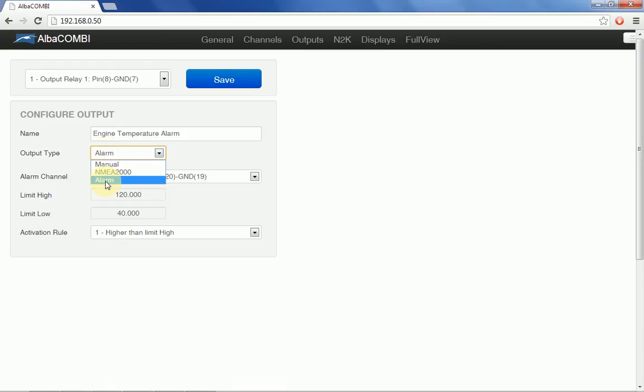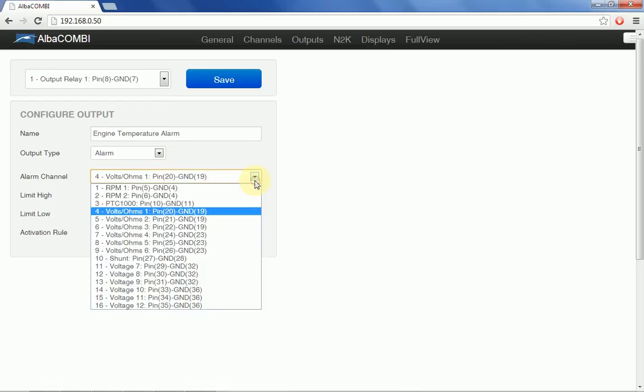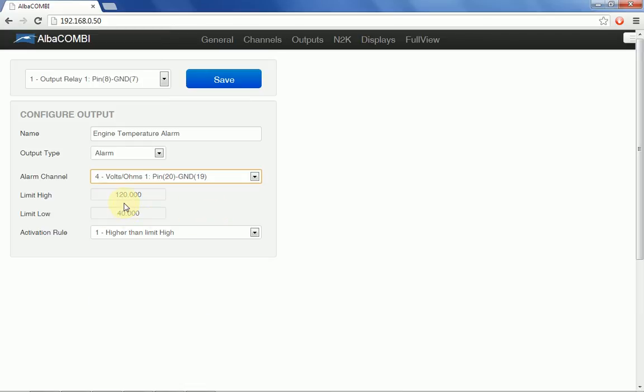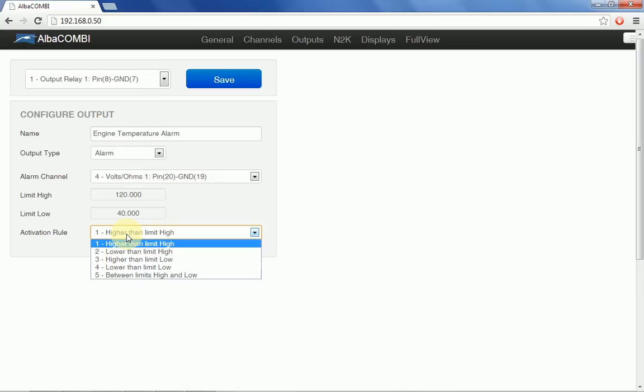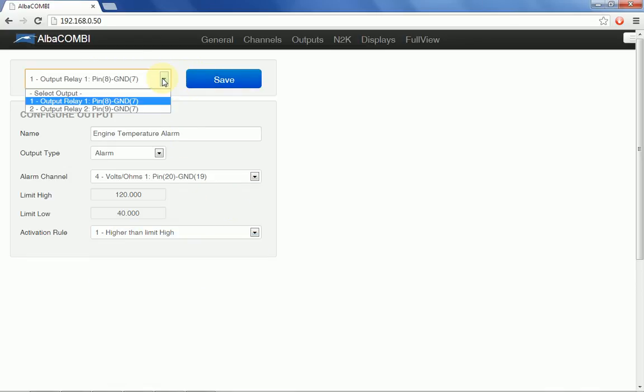Normally you leave this in alarm mode, then select which channel will drive the alarm, and the limits are preset on that channel. You select whether the alarm triggers if the input is higher or lower than the limits, or between the limits. You save it, and you can do this for those two relay alarm outputs. Once you've configured your channels and outputs, there are two things you can do with those inputs.